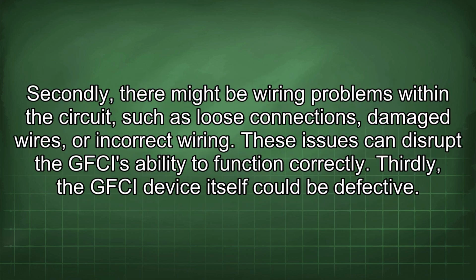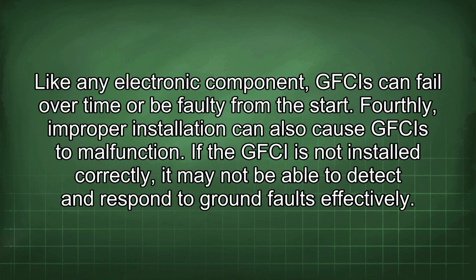Secondly, there might be wiring problems within the circuit, such as loose connections, damaged wires, or incorrect wiring. These issues can disrupt the GFCI's ability to function correctly. Thirdly, the GFCI device itself could be defective. Like any electronic component, GFCIs can fail over time or be faulty from the start. Fourthly, improper installation can also cause GFCIs to malfunction. If the GFCI is not installed correctly, it may not be able to detect and respond to ground faults effectively.